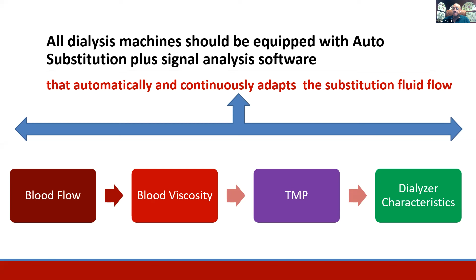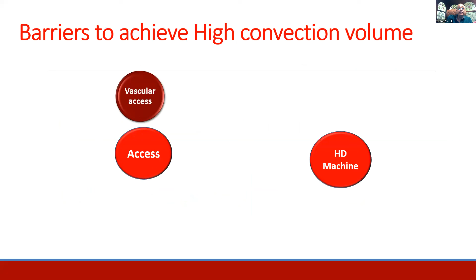Second point, you have to check the sieving coefficient. If you have a sieving coefficient for myoglobin of, for example, 0.1, hemodiafiltration will not solve the problem. You need at least a sieving coefficient of 0.5 for myoglobin to remove sufficient cytokines and others. If you are using a membrane with a low sieving coefficient, hemodiafiltration is innocent. Why doesn't it improve the patient's well-being? This is one of the important issues.